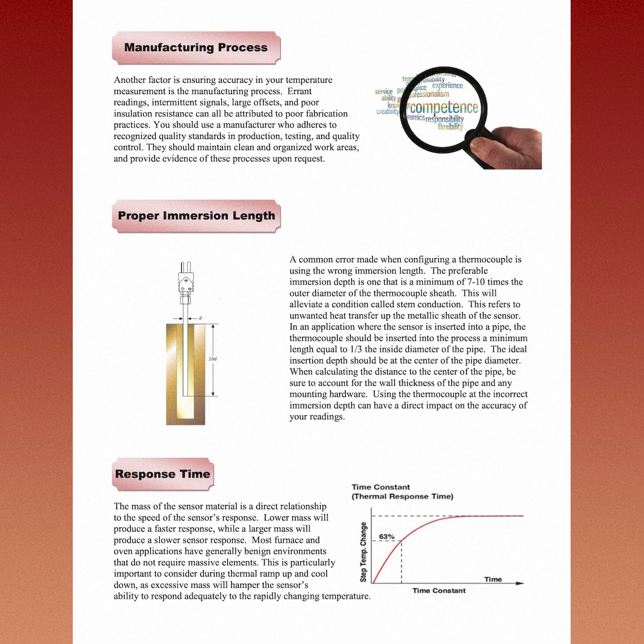Response time. The mass of the sensor material is directly related to the speed of the sensor's response. Lower mass will produce a faster response, while a larger mass will produce a slower sensor response. Most furnace and oven applications have generally benign environments that do not require massive elements. This is particularly important to consider during thermal ramp-up and cool-down, as excessive mass will hamper the sensor's ability to respond adequately to the rapidly changing temperature.